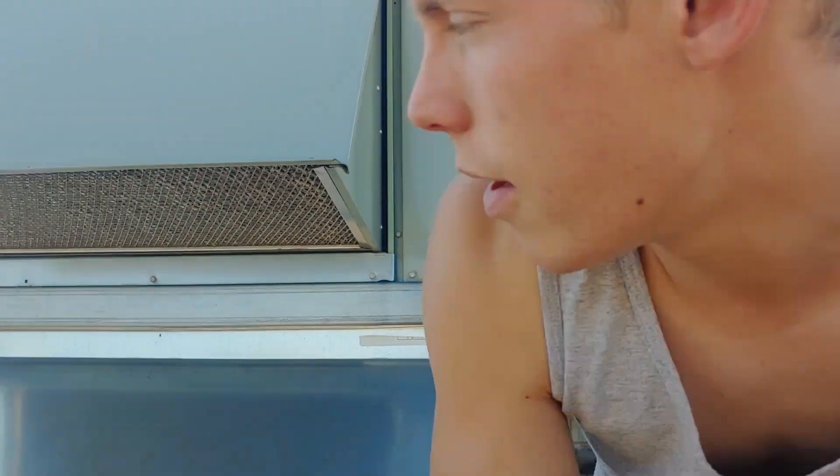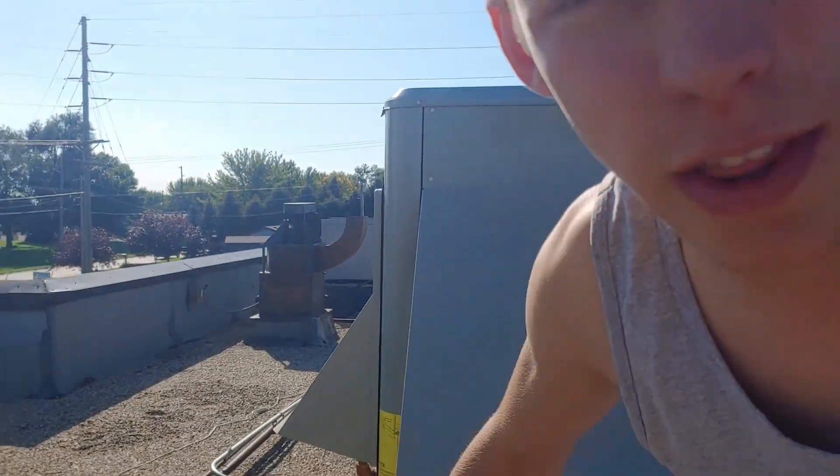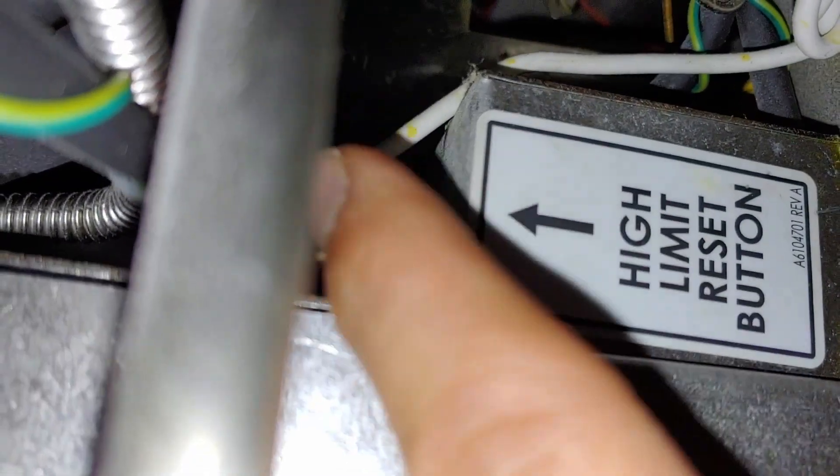So you want to make sure you check your range hood and make sure it's pulling proper air. I'm checking it right over there up on the roof — that's why I'm up here — and we were good to go there. The second switch is the high limit, and that one trips if the fry pot itself ends up getting too warm.